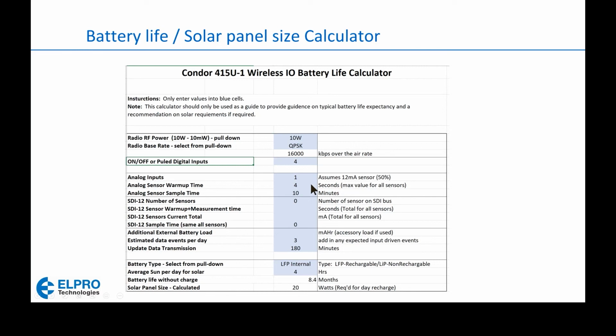With these radio systems, if we're providing power for the 4 to 20 milliamp loop, we want to power the sensor for a period of time to let it warm up and let the reading stabilize. In this case, we're giving the sensor 4 seconds to stabilize. So the radio powers the 4 to 20 loop, the sensor warms up for 4 seconds, then takes a sample, and in this case we're sampling about every 10 minutes or so.